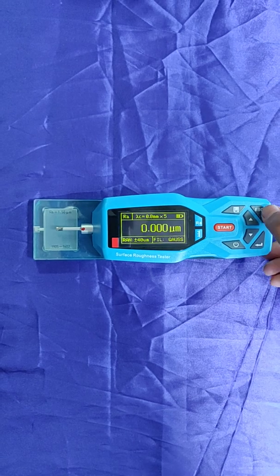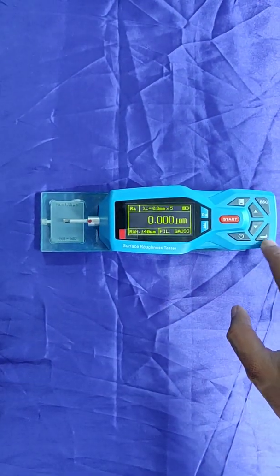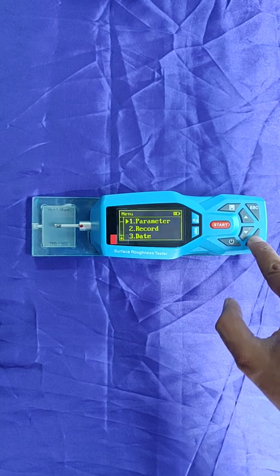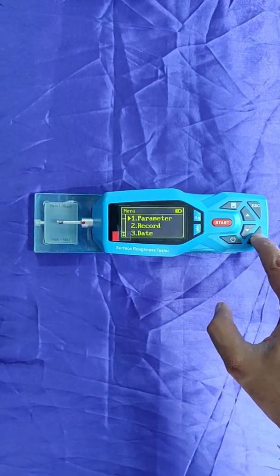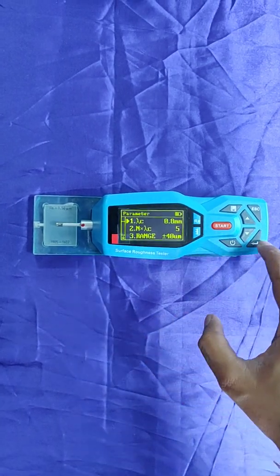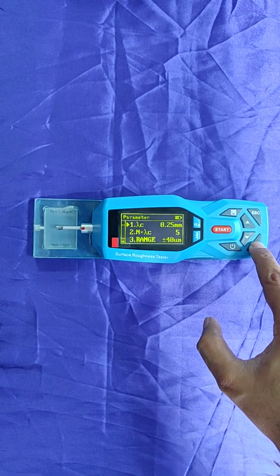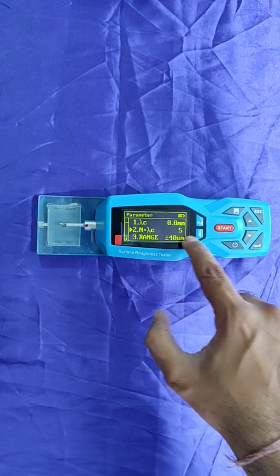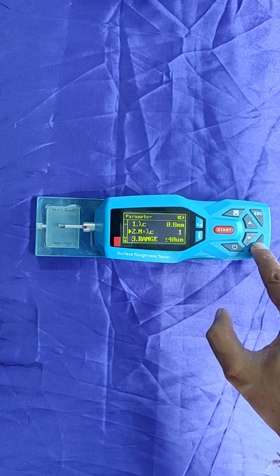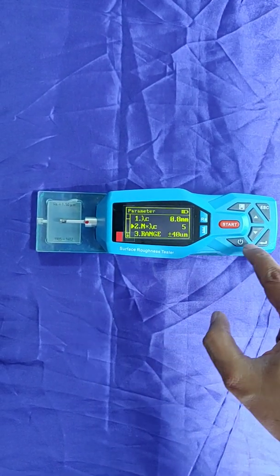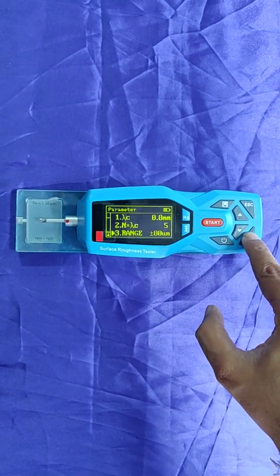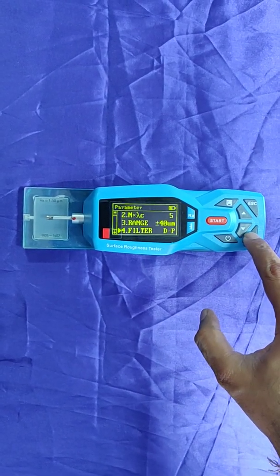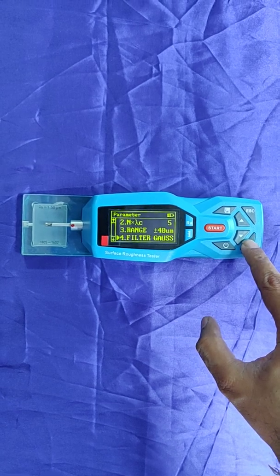First thing is we will explain the user manual. To get into the user manual, we press this enter button. This is parameters. You can change the length like 0.8, 2.5, 0.25 millimeters, but we come back to 0.8 which is the standard. Next is number of cycles: 1, 2, 3, 4, 5. Then range - 40 microns, we can change 80, 20, 40, but this is the standard. Filter: DP, RC, PCRC, but standard is Gauss.